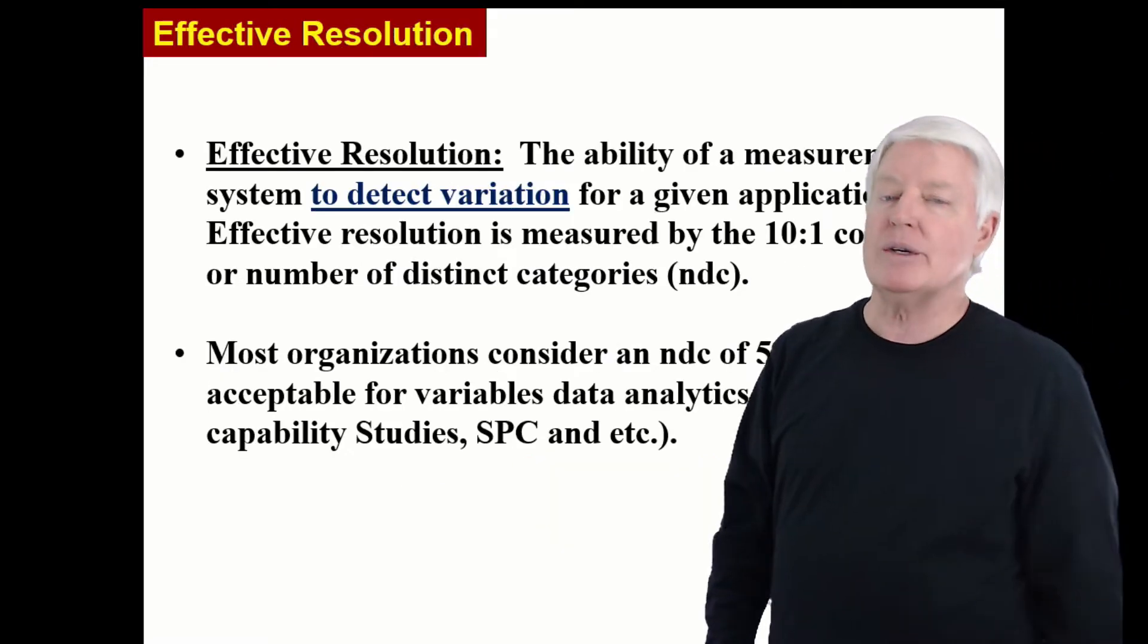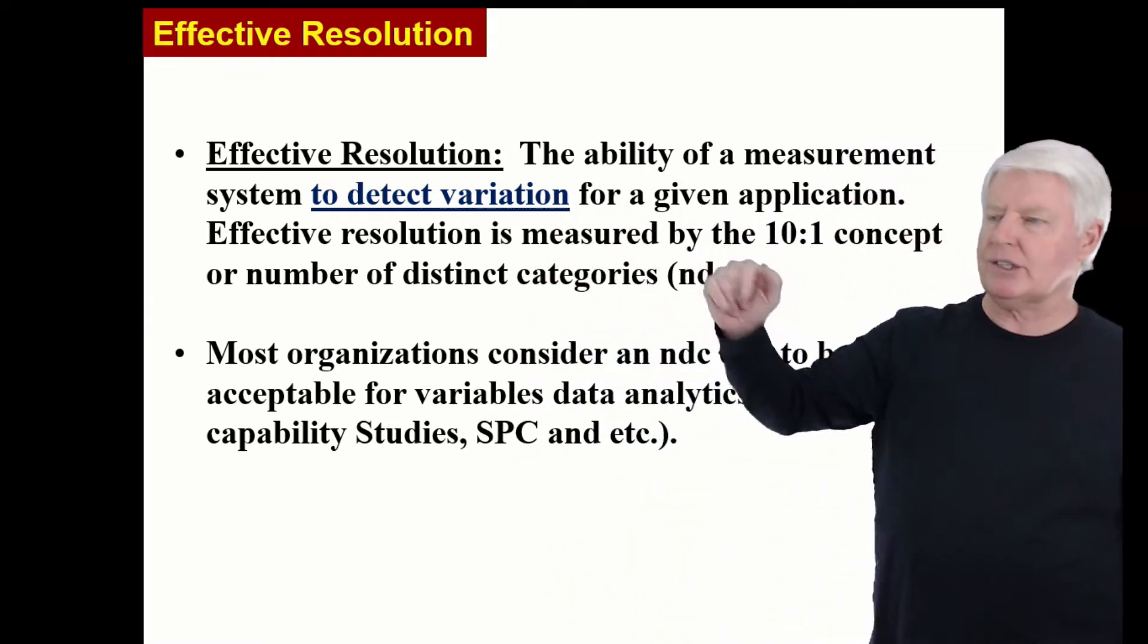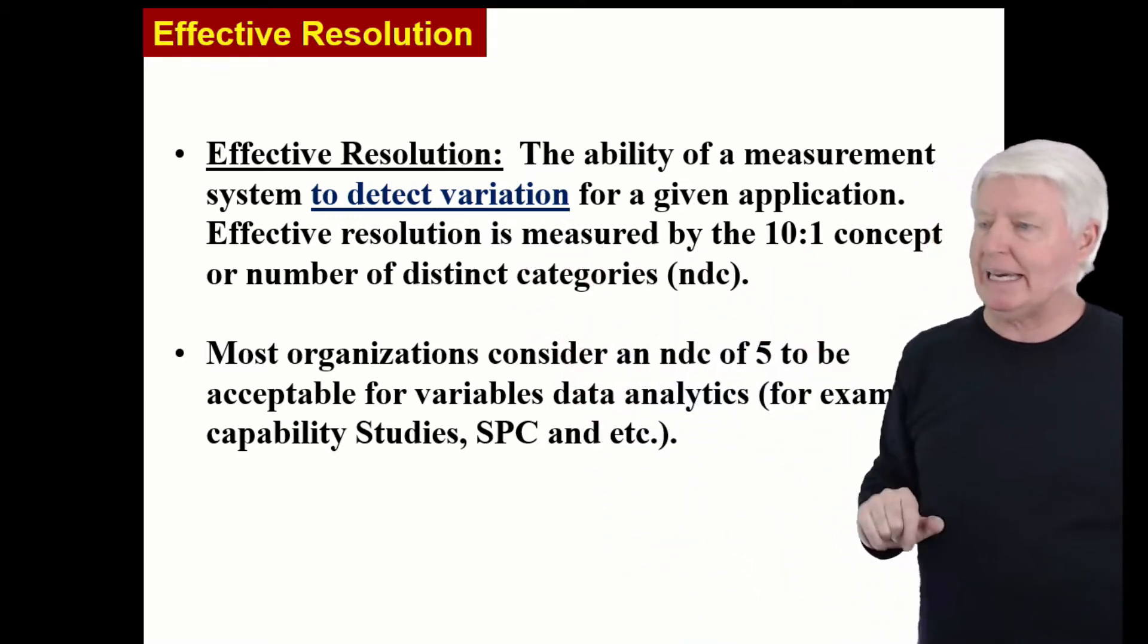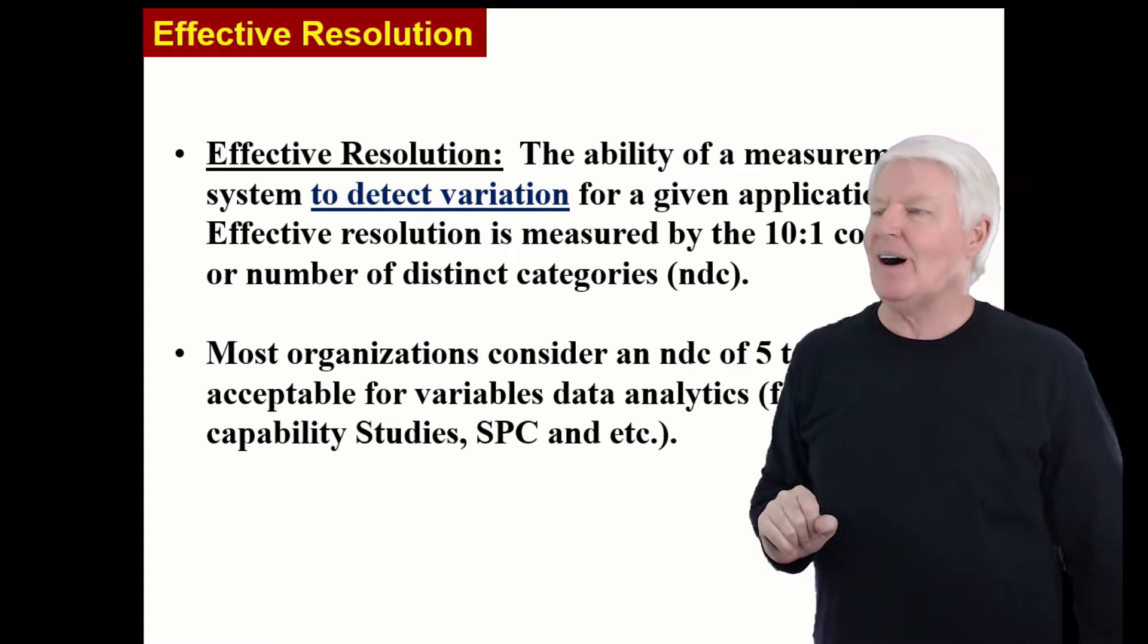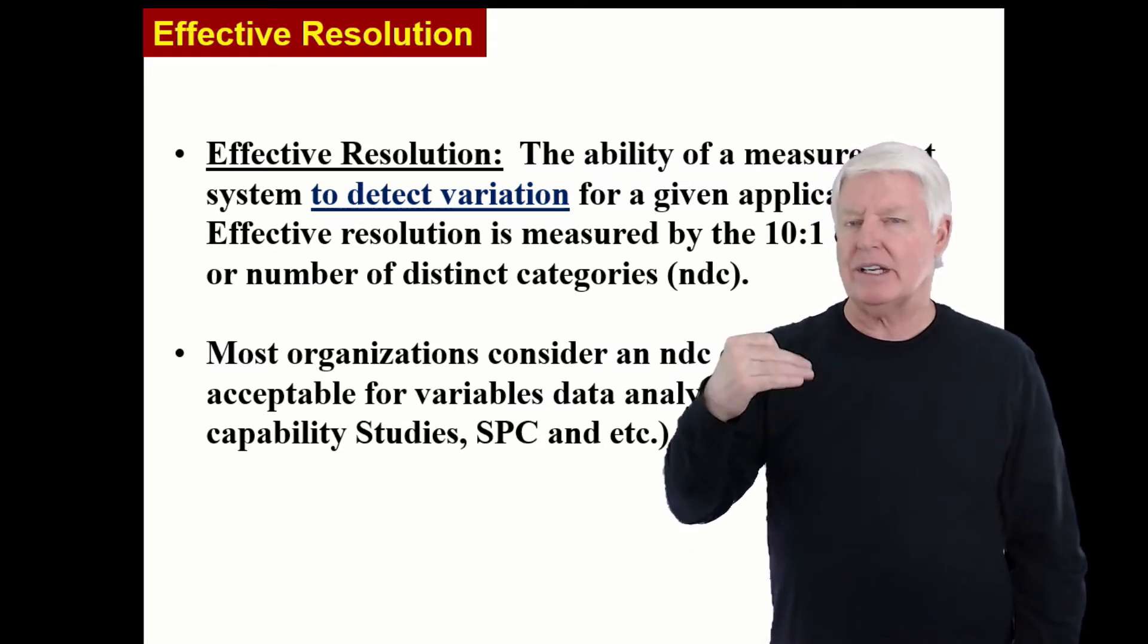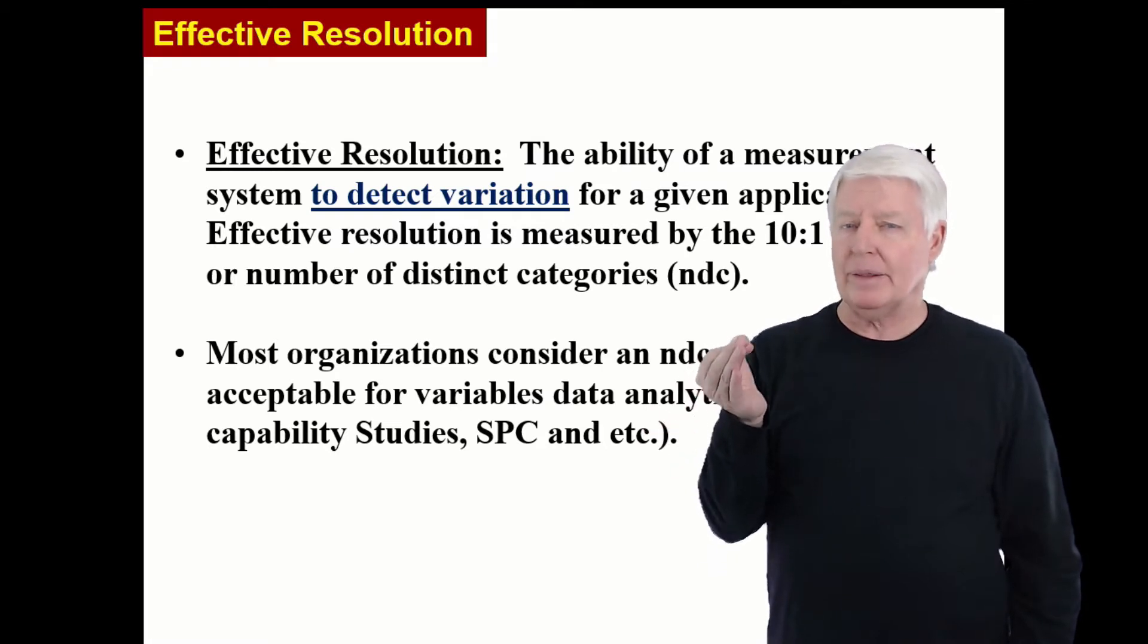Now let's go into effective resolution. The ability of a measurement system to detect variation for a given application. Effective resolution is measured by the 10 to 1 concept or number of distinct categories. So effective resolution, let me explain it this way: effective resolution, your instrument is sensitive enough or has enough resolution that you can pick up on the variability.